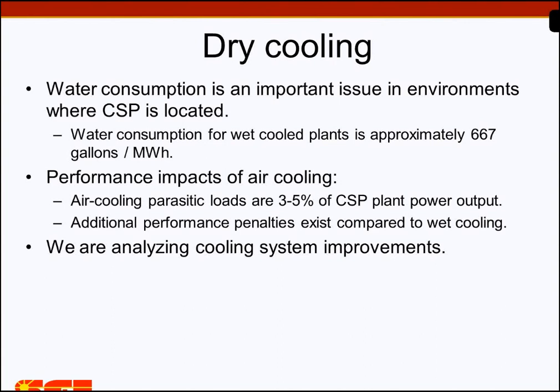Focusing on concentrating solar power and dry cooling: water consumption is certainly an important issue where CSP is located in arid desert areas with high direct irradiance resources. A benchmark number — the water footprint for electricity consumption overall is said to be about half a gallon per kilowatt hour, or 500 gallons per megawatt hour. For wet-cooled power plants it's a bit higher — you can derive this from the enthalpy of vaporization of water — and it's a big number.